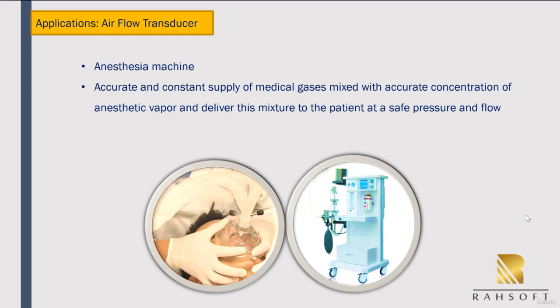As mentioned before, they can be used for ventilators, but also for anesthesia machines. An accurate and constant supply of medical gases, mixed with an accurate concentration of anesthetic vapor, can deliver this mixture to the patient in a safe pressure and flow.